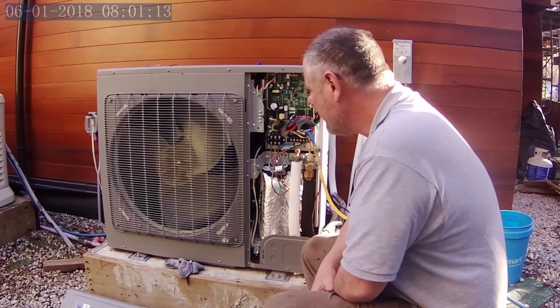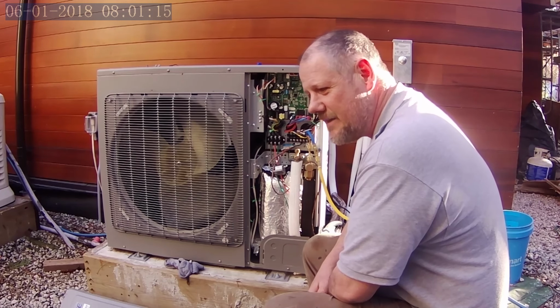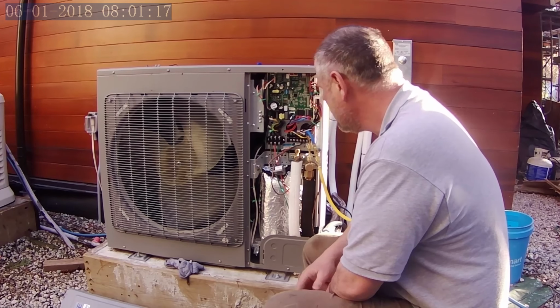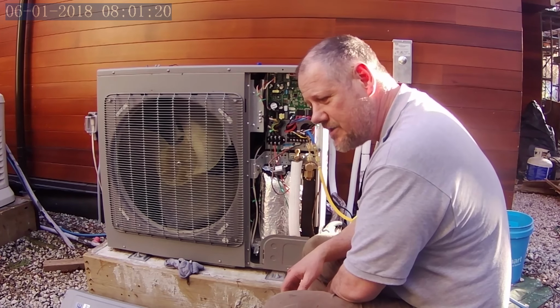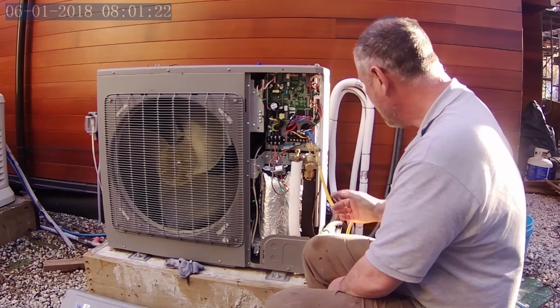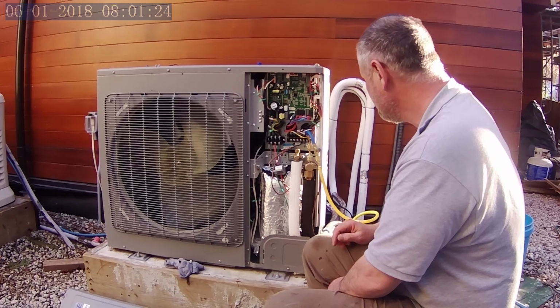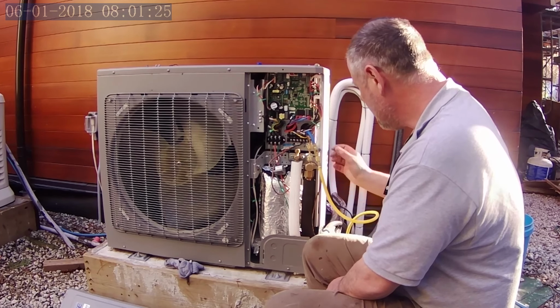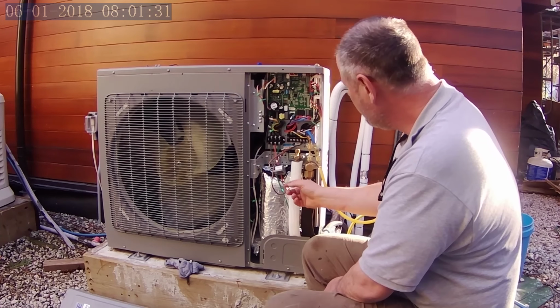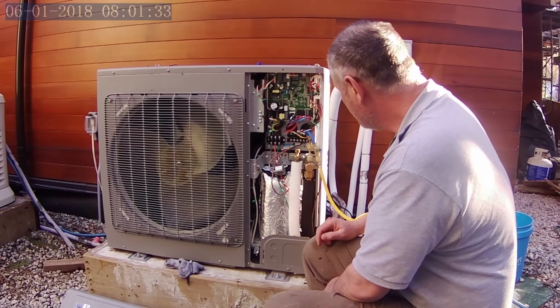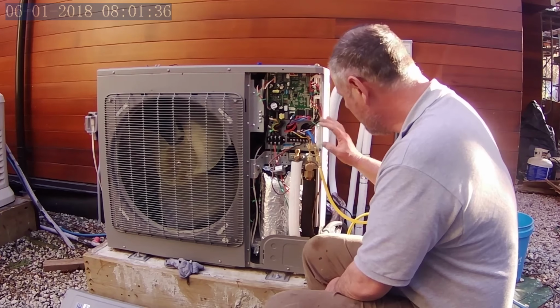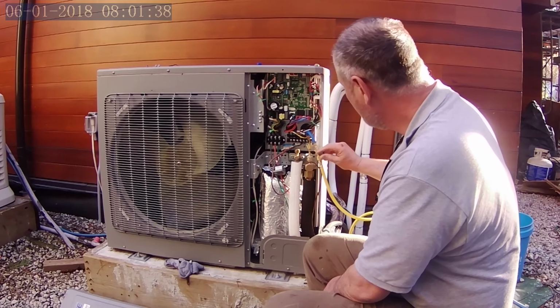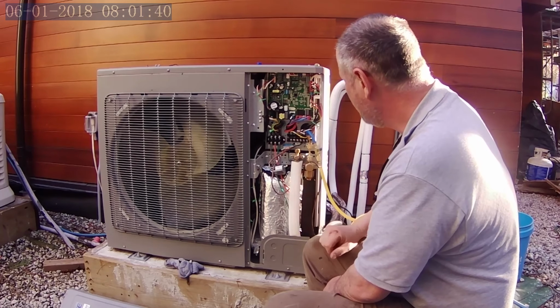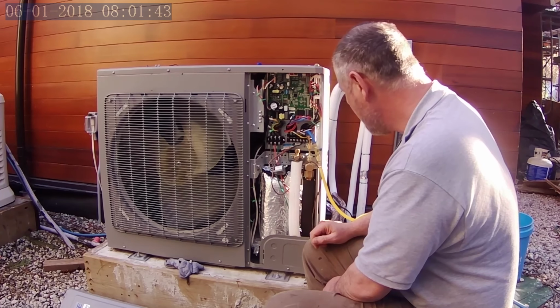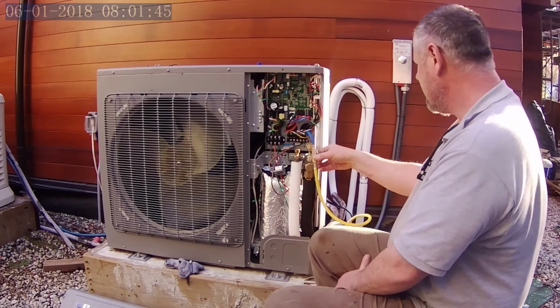And Benoit has indicated to go for it. So I'm going to turn the vacuum pump back on just to make sure that we're not introducing any air into the system as we do all of this, and make sure there's still a negative charge on the hoses here. And then we are going to slowly open up. We're going to create a vacuum, we're going to block it off, and then we're going to slowly open up the liquid line and let the refrigerant out. So let's go ahead and do that.